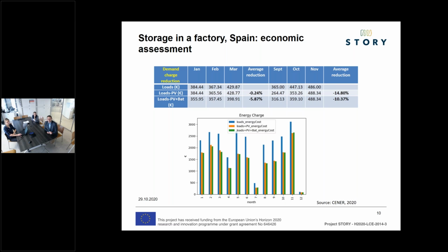For the winter months of January, February, and March, the introduction of a PV system does not really lead to any demand charge reduction. This is due to the fact that in Spain, the high tariff period starts at 5 o'clock in the afternoon, so it does not really coincide with the PV generation.